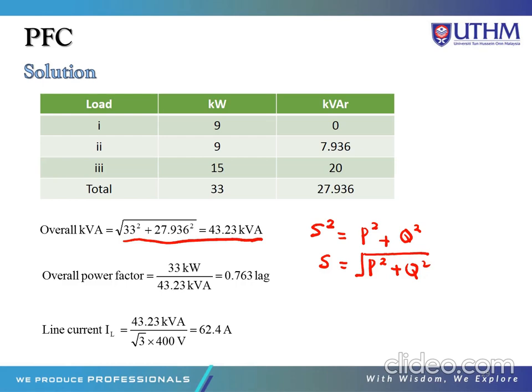Then we have to calculate the overall power factor. Using the formula, power factor is equal to P divided by S, P total divided by S total. So we get 0.763 lagging. And lastly, we calculate the line current. To get IL, we divide S by the voltage, so we get 62.4 A. We also have to divide by square root 3 because I line represents the single phase current.